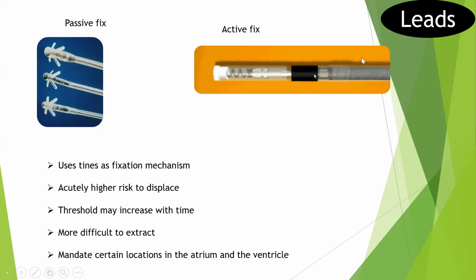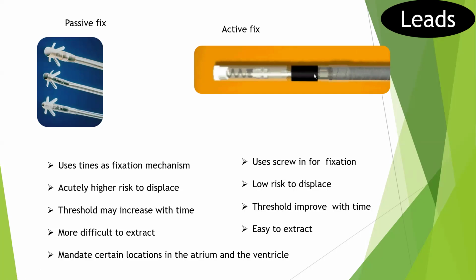On the other hand, the active fixed lead uses an active screwing mechanism. Basically, the tip of the lead has, as you can see here, a screw inside the lead, and that screw can come out from the tip of the lead and connect the lead to the myocardial tissue. Because of that, it has a low risk of displacement. The threshold will improve with time. Most of the time, you will have a high threshold sometimes during the implant, and once the patient goes through the acute phase of pacemaker implant, the threshold will improve. The same thing, sensing improves as well. And it is easy to extract. In my personal experience, you can extract an active fixed lead even more than 1 year from the date of the implant without a need for laser lead extraction.